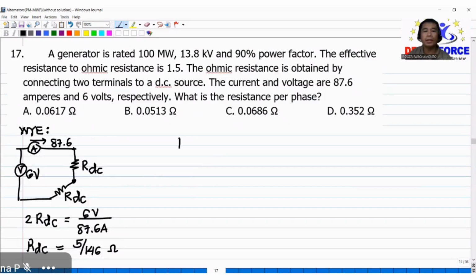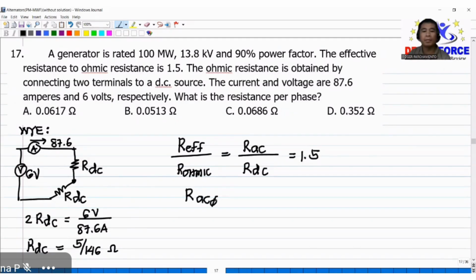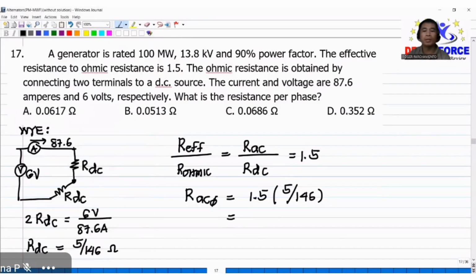Then the ratio of the effective resistance to the ohmic resistance. This is RAC, the effective value of the resistance, divided by RDC. That is equivalent to 1.5. So therefore, what is the resistance per phase, or effective resistance per phase? So 1.5 multiplied by 5/146. 1.5 times 5 divided by 146. So that is 0.05137 ohm. That corresponds to letter B.